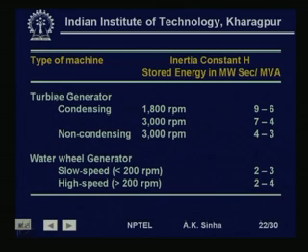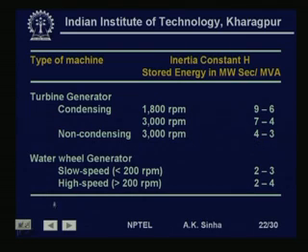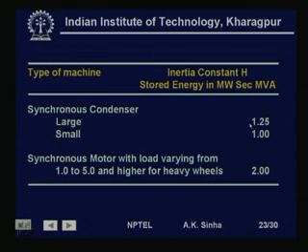H is used instead of M or J because H values fall within a known range for different machine types. For turbine-generators with condensers at 1800 rpm, H is 6–9 seconds; at 3000 rpm, 4–7 seconds; non-condensing, 3–4 seconds. For hydroelectric generators, H is 2–4 seconds depending on speed. For synchronous condensers, H is about 1–1.25 seconds, and for synchronous motors, about 2 seconds.